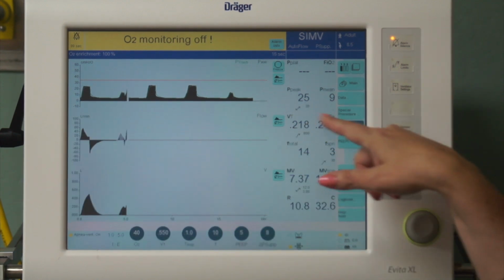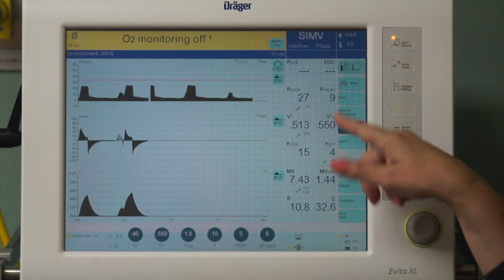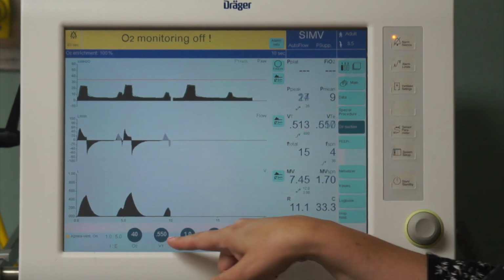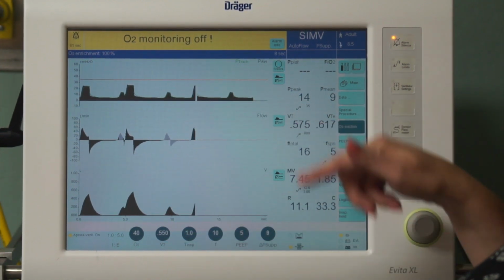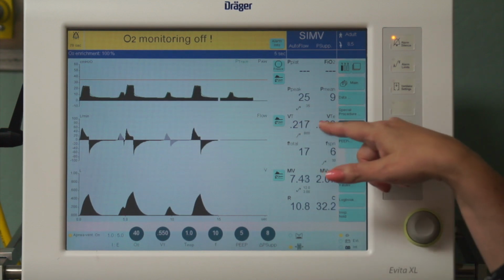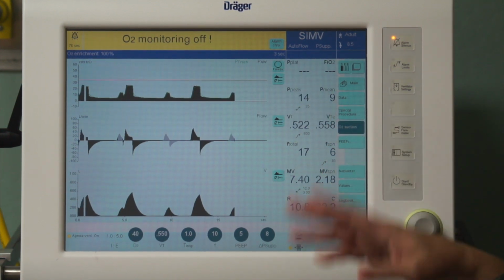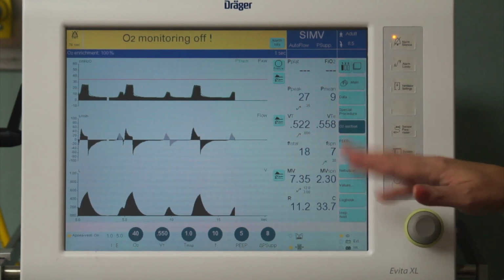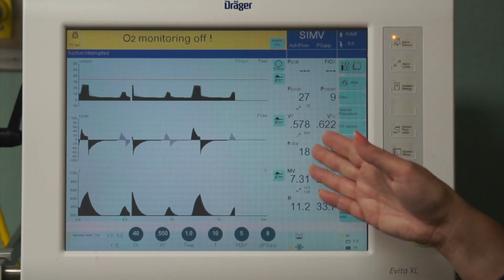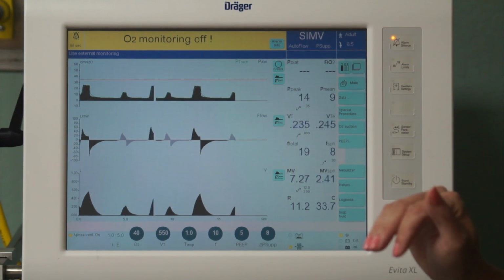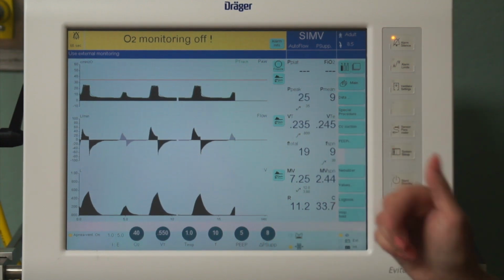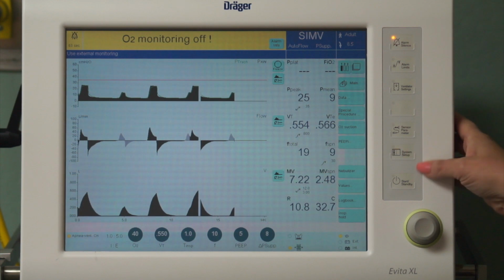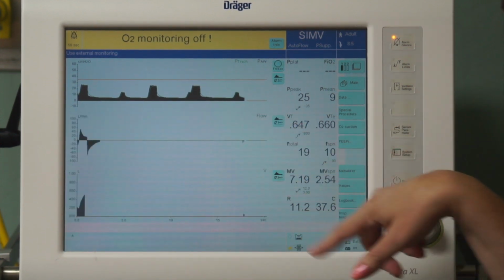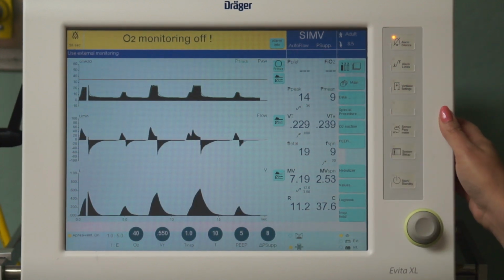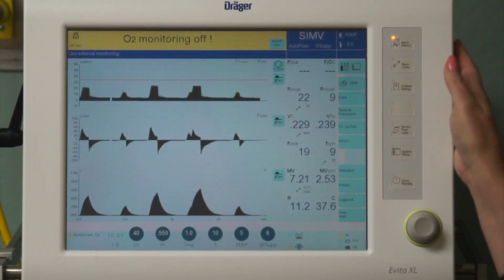And that's especially important to do if your volumes are not making sense. Like right now I have this patient set at 550, my mandatory volumes are greater than that, and my spontaneous volumes, because we're in pressure support, are in the 200. So it all looks like it's making sense. If at any point the numbers just look wonky, you want to calibrate your flow sensor. A lot of times that's what that is. So that's our sensors. And that is the Draeger in a nutshell.